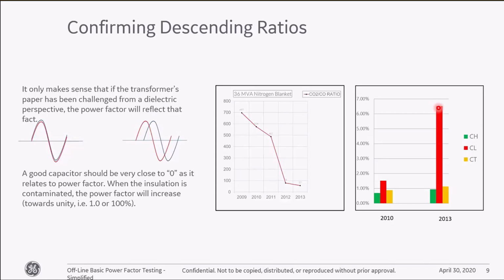Okay, so when will it fail if you just left it and put it back in service? There's no real right answer to that question. It may fail the minute you put it back. It might fail in a bridge after it reaches 2%. It might fail in a bridge after it reaches 1.5%. In this case, obviously, it could go at least up to 6.5%, but I wouldn't expect it to live long in this condition. So knowing exactly how long, who knows? Nobody really knows the answer to that.